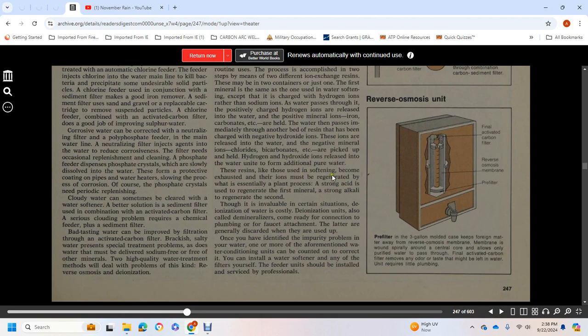These resins, like those in the softener, become exhausted, and the ions must be regenerated, which is essentially a plant process. A strong acid regenerates the first resin, and a strong alkali regenerates the second. Though it is invaluable in certain situations, deionized water is costly. Deionization units, also called demineralizers, come ready for connection to plumbing or faucet attachment. The latter are generally discarded when they are used up.